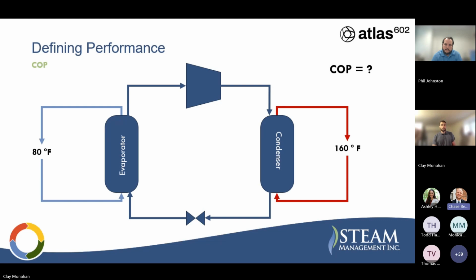Okay, so that actual is like your actual power input compared to your actual thermal output, including parasitic losses, any other inefficiencies in the system, right? Yeah, we'll get into some math examples here, but it's basically what's your actual COP that you can achieve versus what's the theoretical maximum. Because you can do the math on what the theoretical maximum could be, but you're never going to achieve that. You're only going to achieve some percentage of that.